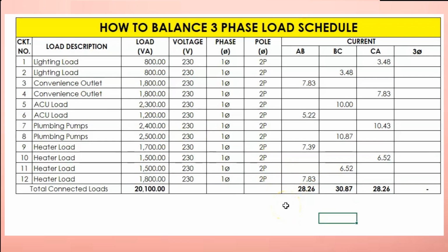So the advantage of balancing the load schedule is to avoid overheating of lines A, B, C. So sir, what if line AB is 50 amperes while the rest is 30? That's a big gap. For sure, if this line AB operates 24 hours, one line will overheat or overload. That's bad, or dangerous, for the panel board system. It could either cause fire or trip the circuit breaker. If that's the case, please consult an electrical practitioner for that scenario.